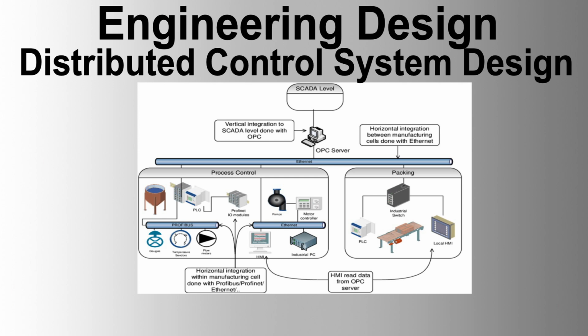Standard software. The following software packages must be provided as a minimum: system software, system configuration database, diagnostic software, interfacing software for PLC and external equipment, software for implementing advanced process control strategies if required. System diagnostics. The DCS must use equipment incorporating self-test and fault diagnostic systems. Failure of any component must initiate an alarm at the operator workstation, indicating the type of fault. The diagnostic system must detect faults in the CPU, memory, power supply, I/O cards, I/O points, MCB trips, fuse failures, data link communications, and serial link failures.